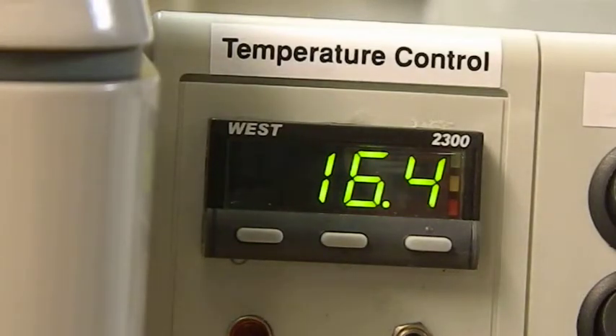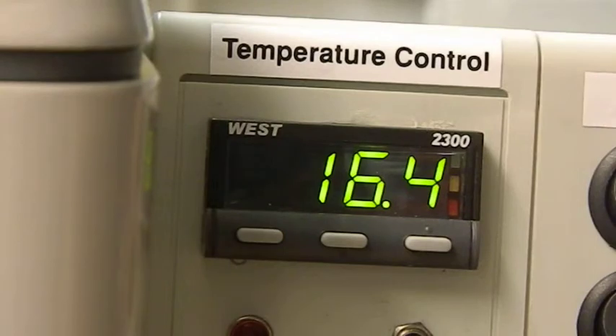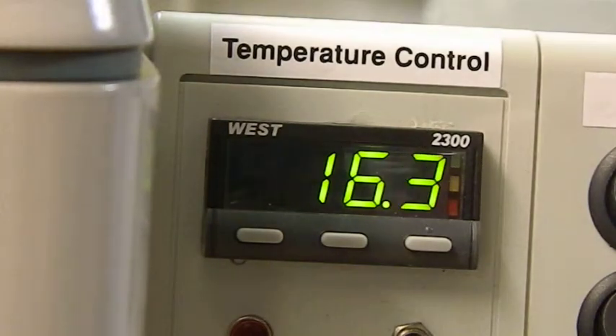Okay, so the first thing to do is to write down on a piece of paper 16.4, which is in fact on this machine what the set point has been set to, so it is controlling at 16.4, the set point that it's asked to. Inside the machine, if I have a look, the thermometer is reading 16.1, so there's 0.3 of a difference. That's not unusual, it's well within spec, and we'll take that out now in the calibration.